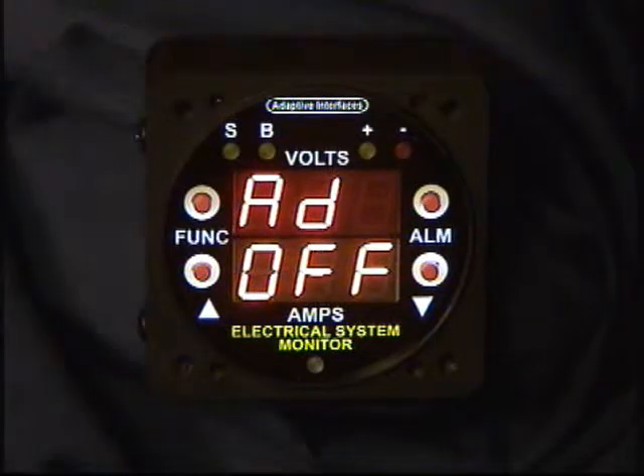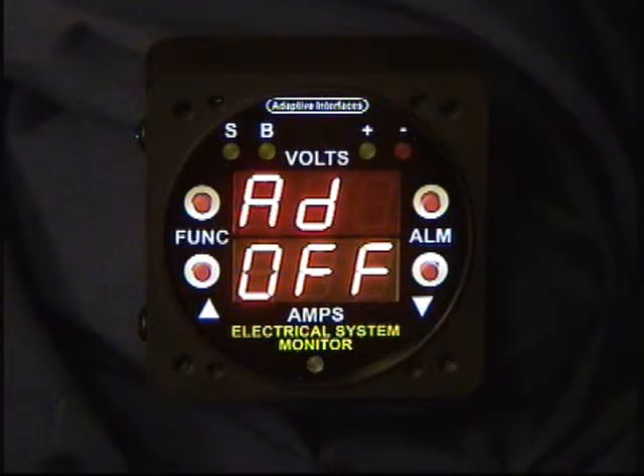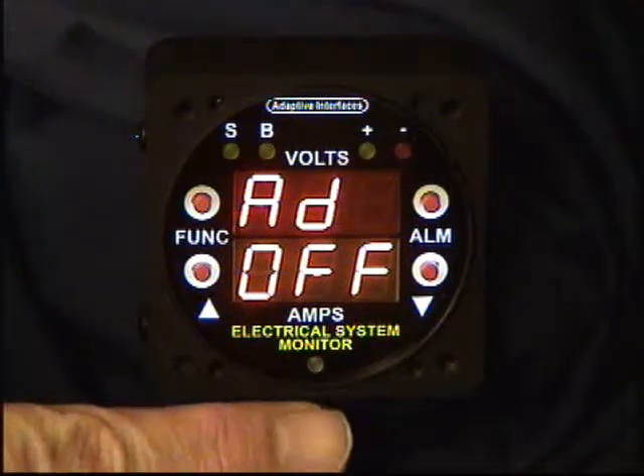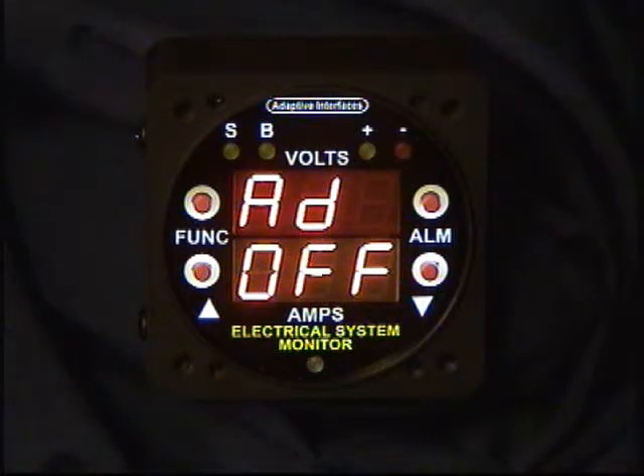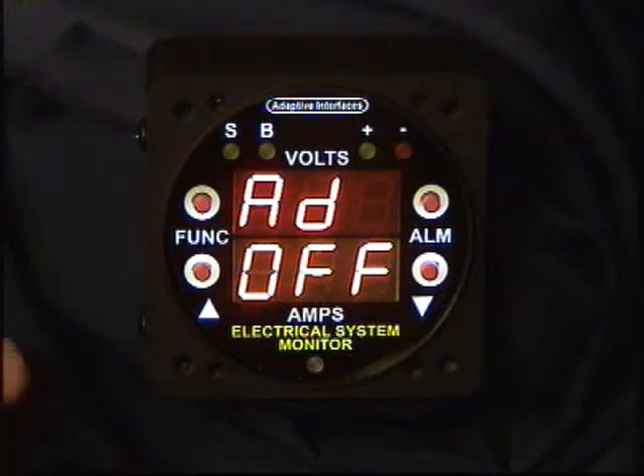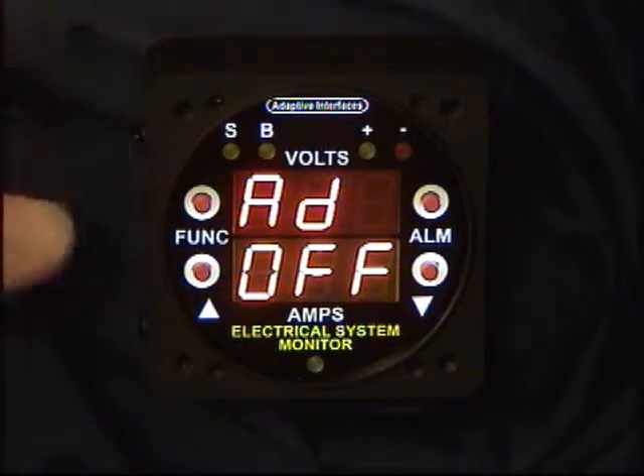The next function is an auto dim function. Right now it's turned off. The auto dim function works when brightness is being controlled by the front panel controls, allowing the photo cell to automatically dim the instrument in a low light condition or brighten it in a high light condition, after which you can still use the up/down arrows to control display brightness.